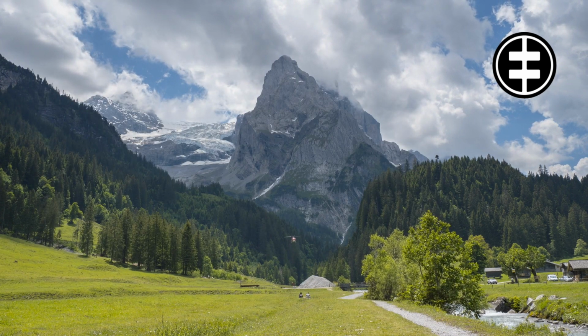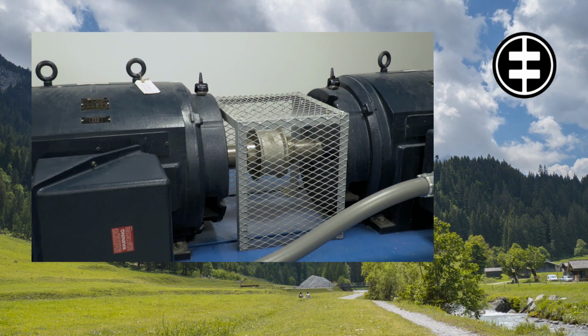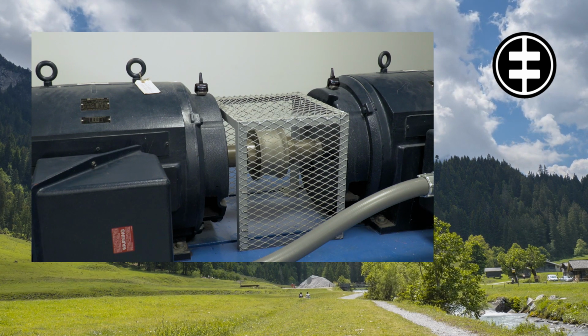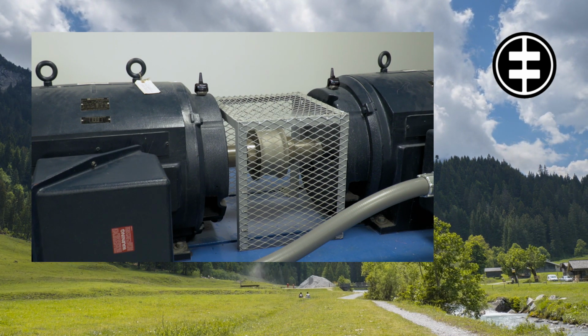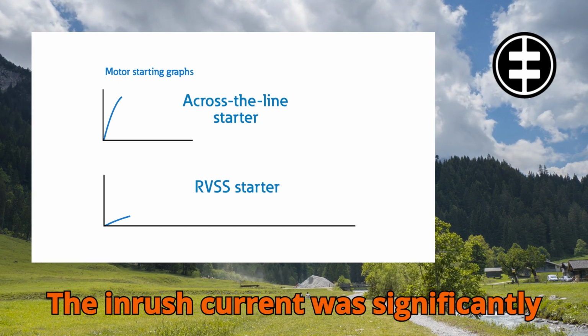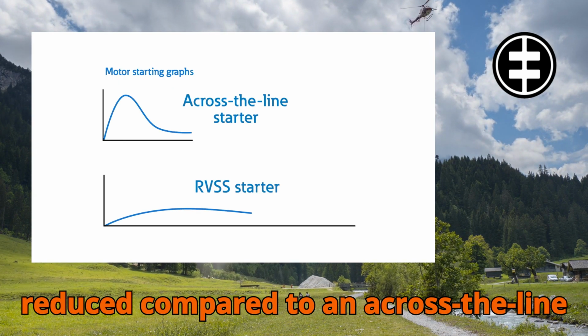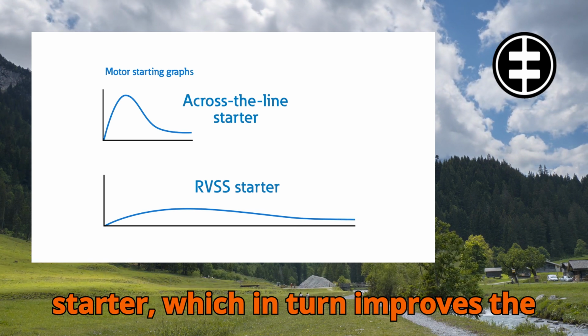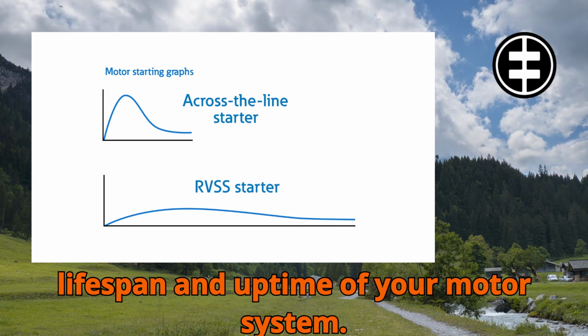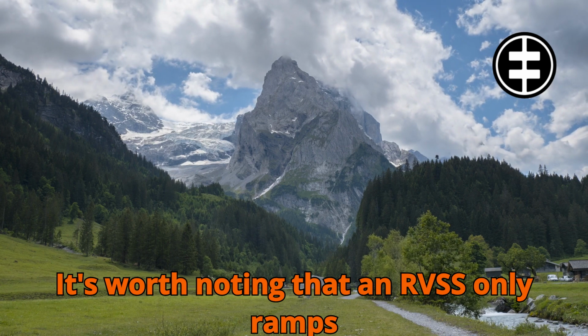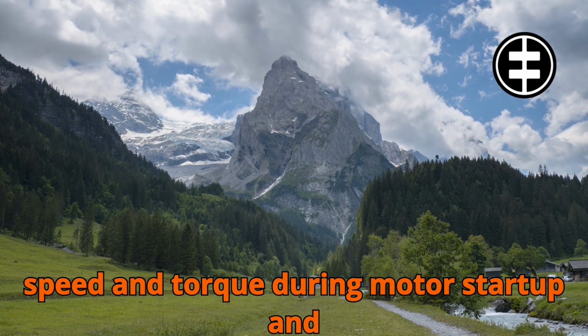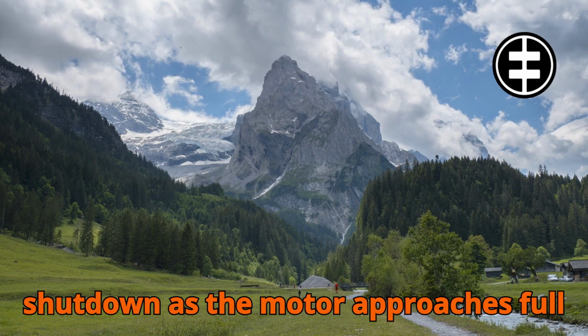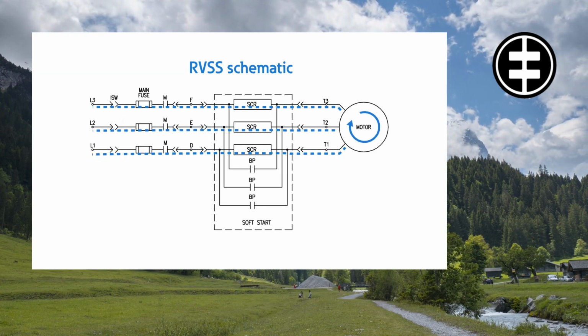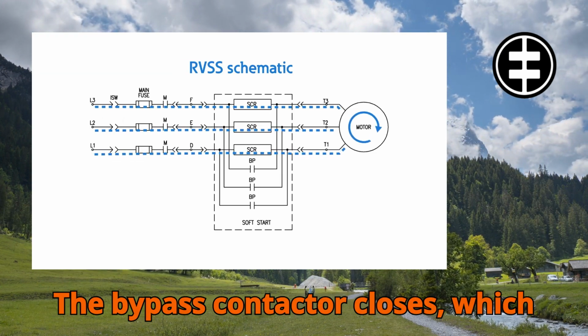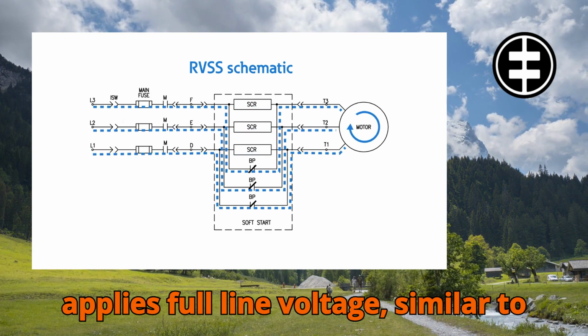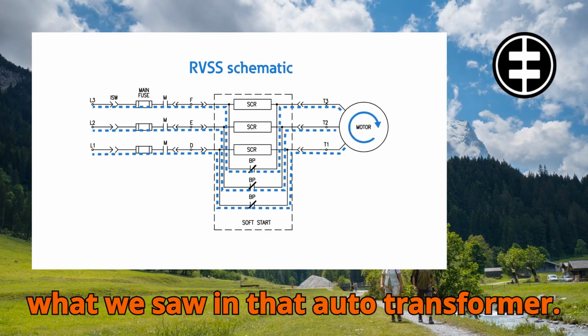Hear that smooth ramp up? The inrush current was significantly reduced compared to an across-the-line starter, which in turn improves the lifespan and uptime of your motor system. It's worth noting that an RVSS only ramps speed and torque during motor startup and shutdown. As the motor approaches full speed, the bypass contactor closes, which applies full-line voltage, similar to what we saw in that auto transformer.